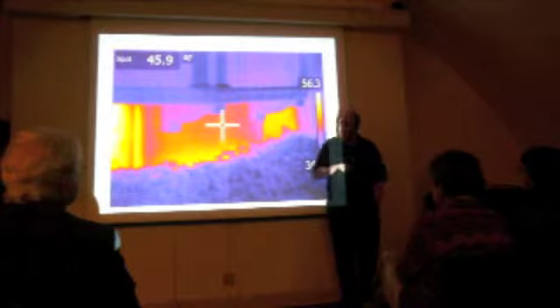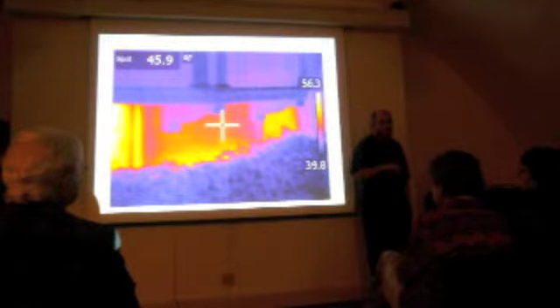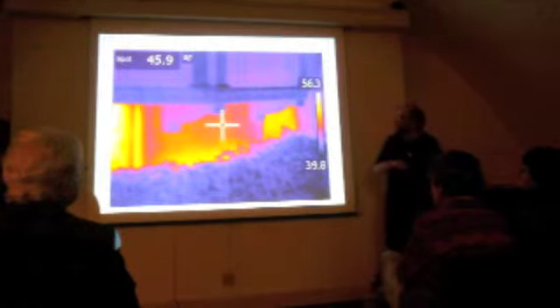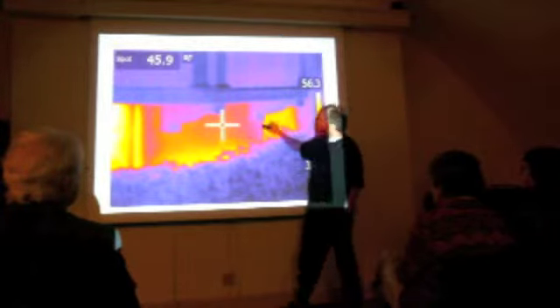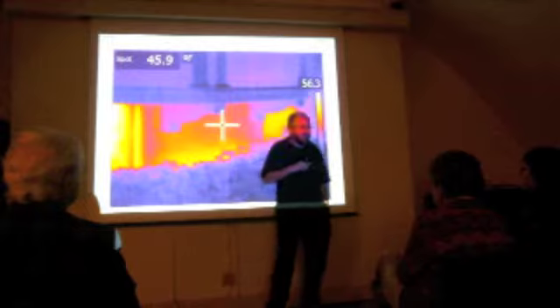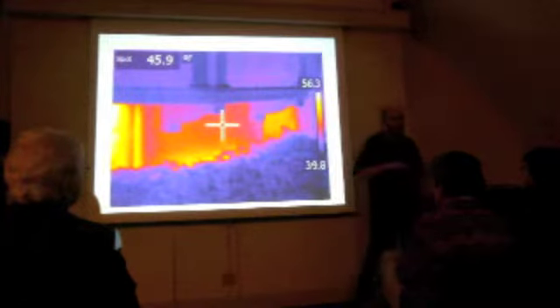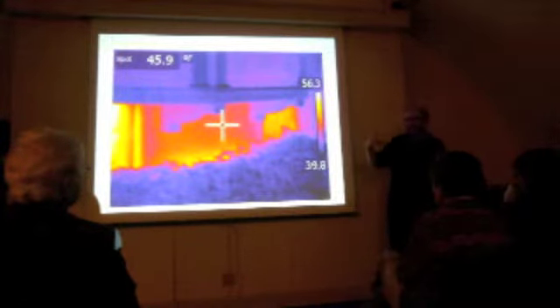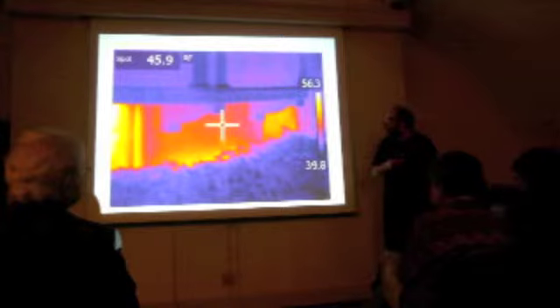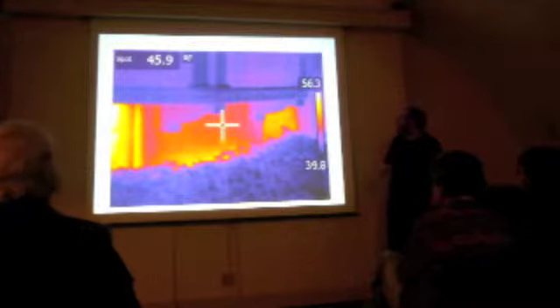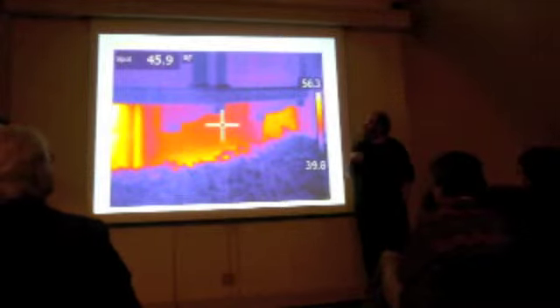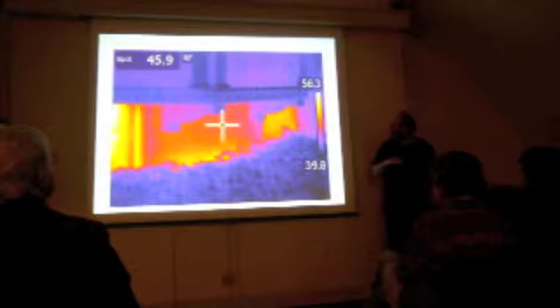The exterior of the building, the upstairs parts of the building are pretty well insulated. They're showing up as pretty blue. This is the basement wall that's above grade. And what you're seeing is that the basement wall is not as insulated as the upstairs. And so essentially all the way around that rim, wherever you see the brick, the building is leaking heat at a much higher rate. You can see that it's about 10 degrees warmer in some places than the rest of the building.